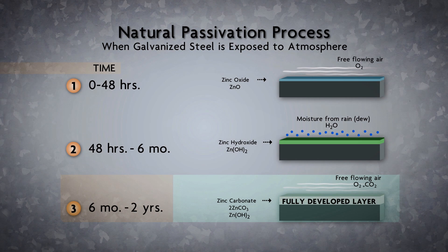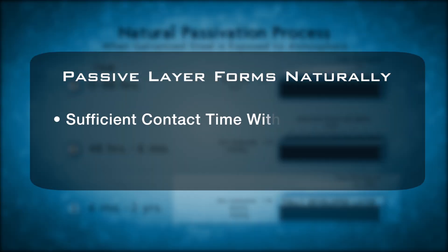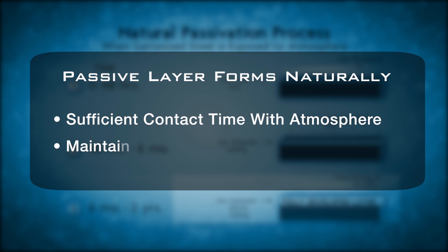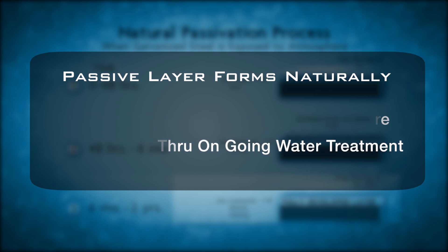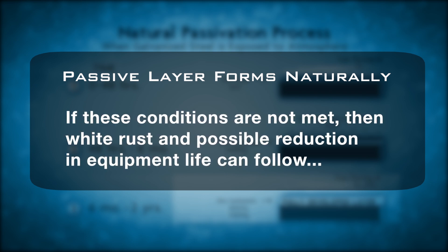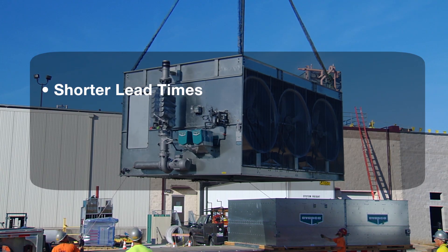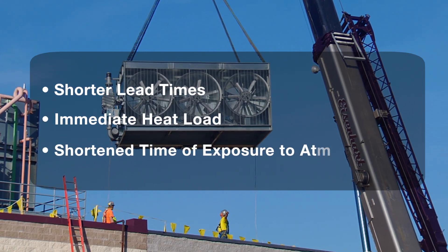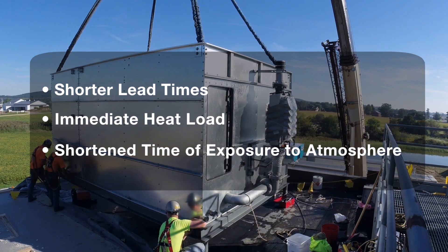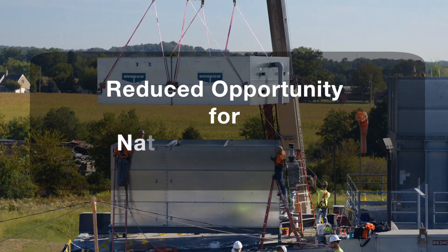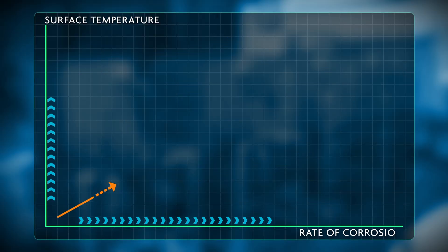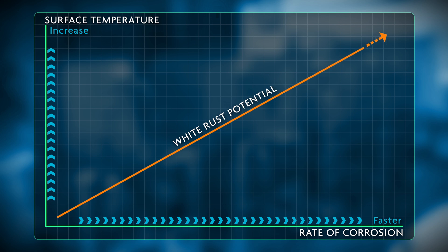So now we have established that white rust has become a problem for new galvanized steel in the evaporative cooling industry. To prevent it from causing serious damage, the equipment needs to be protected. Remember, this protective passive layer forms naturally when there is sufficient contact time with the atmosphere, and it also has to be maintained through ongoing water treatment. If one or both of those conditions aren't met, then white rust and possible reduction in equipment life can follow. In recent years, customer preferences for shorter lead times and their requirement for immediate heat load has shortened the time that new galvanized evaporative cooling equipment is exposed to the atmosphere prior to initial water circulation. This reduces the opportunity for natural passivation to occur. Higher temperatures increase the potential for white rust when new equipment is commissioned with immediate load.